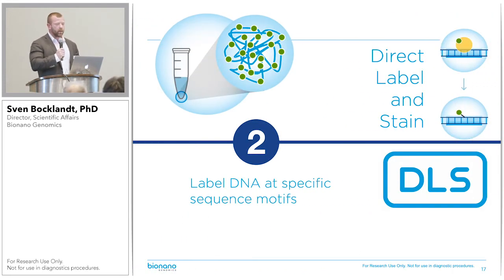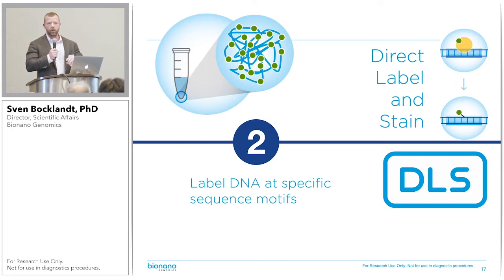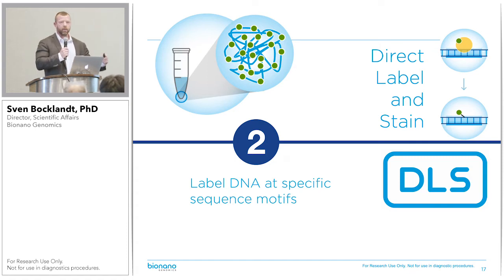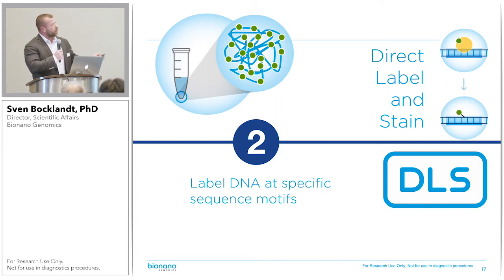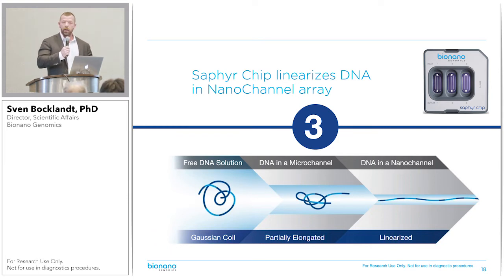Once we have these molecules, we label them with a single enzymatic reaction that attaches a fluorophore directly to the DNA at the location of a six base pair sequence motif — just a single sequence motif all throughout the genome labeled in an enzymatic reaction, no probes. We end up with long DNA molecules that have a fluorescent label attached. Our instrument uses electrophoresis to move these molecules into nano-channels and linearize them, and when linearized, they're uniformly stretched and we get all the information we need just by taking a picture.